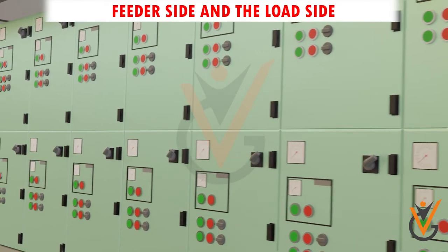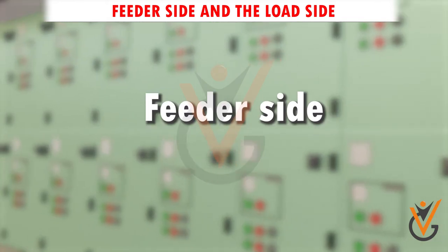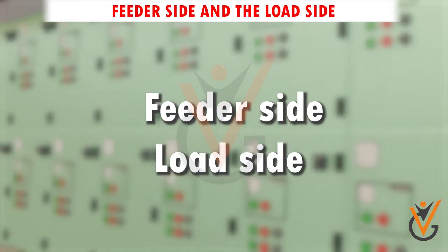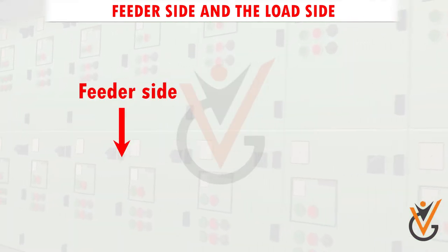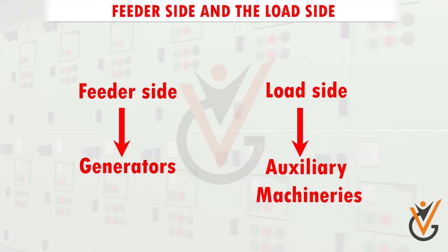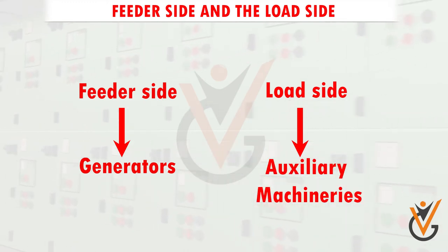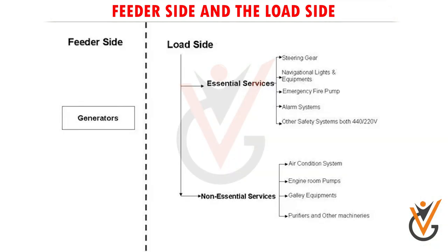The distribution system can be divided into the feeder side and the load side. The feeders are the generators, and the loads are the various shipboard auxiliary machineries. The load side is further divided into essential and non-essential services. Essential services are very critical auxiliaries which directly affect the safety of personnel and the ship in terms of navigation and propulsion.